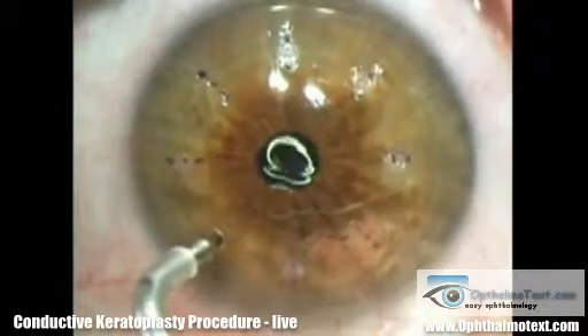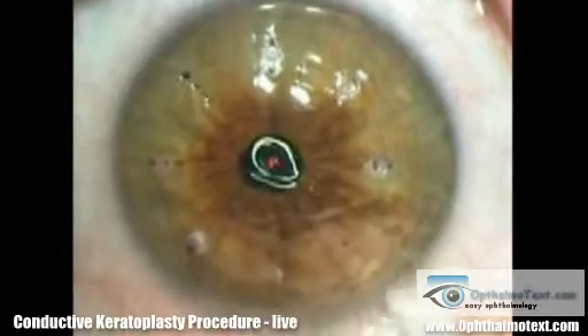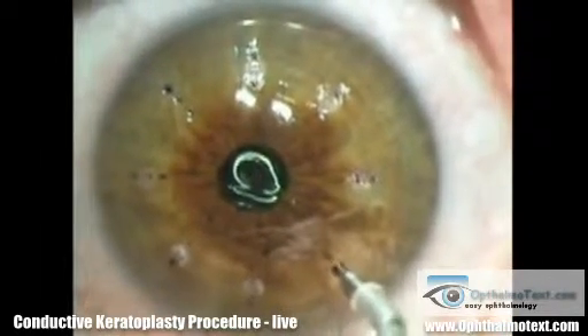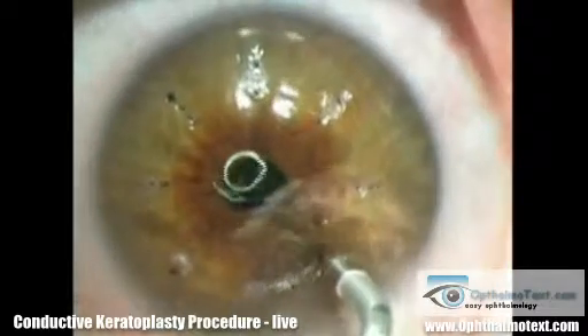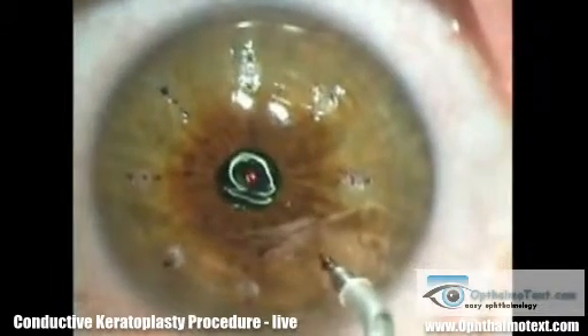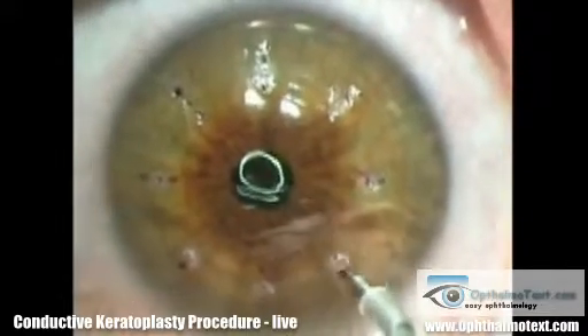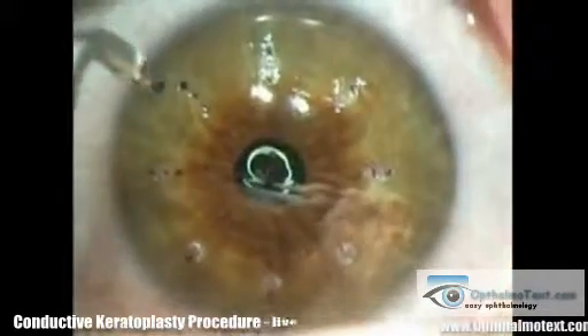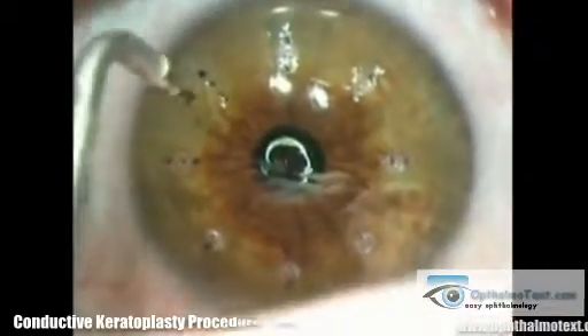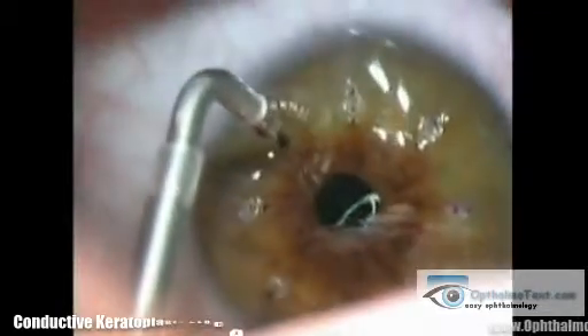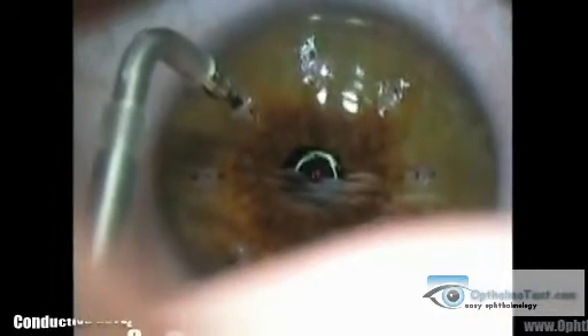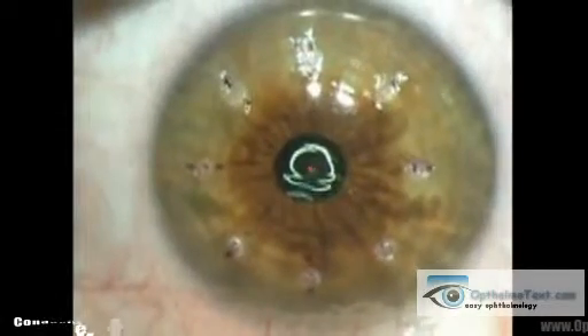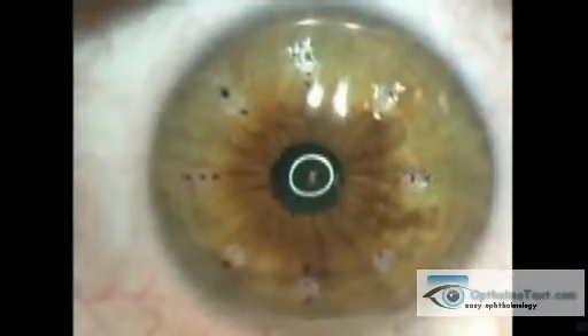Biomechanical stretch is released by allowing there to be no compression forces at the time of the beginning of the radiofrequency pulse. As the pulse is being delivered, which is starting right now, the probe is gently pushed posteriorly as the cornea contracts away from the delivery of the radiofrequency pulse. This consistent maneuver with each of the 8 spots allows the radiofrequency pulse to have a maximum effect, a consistent effect, allowing the patient to have a reliable post-op refraction and minimal induced cylinder.